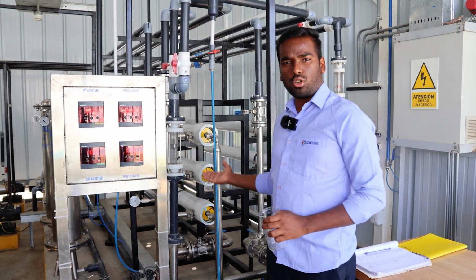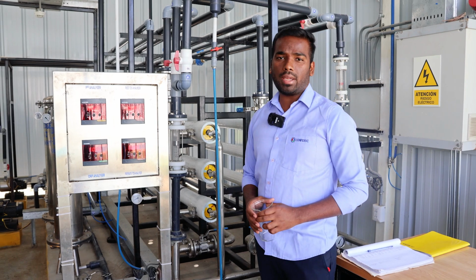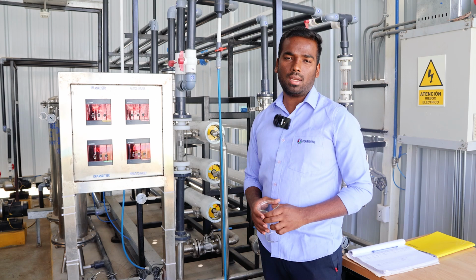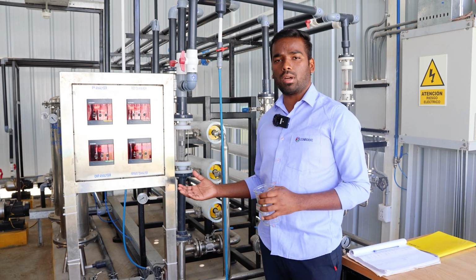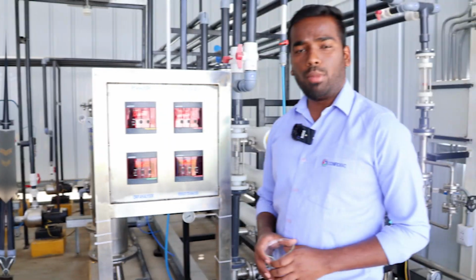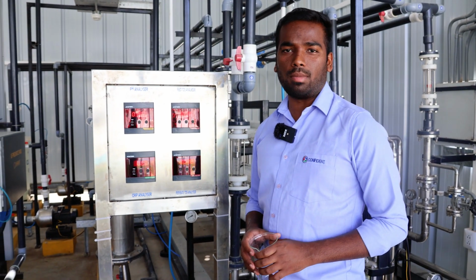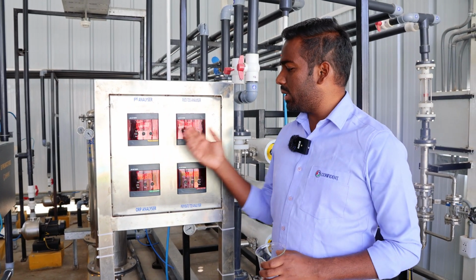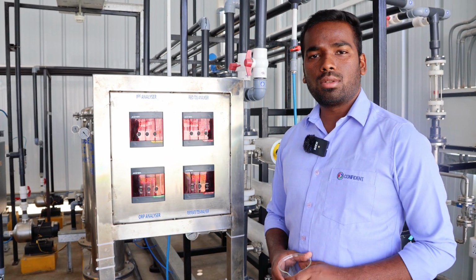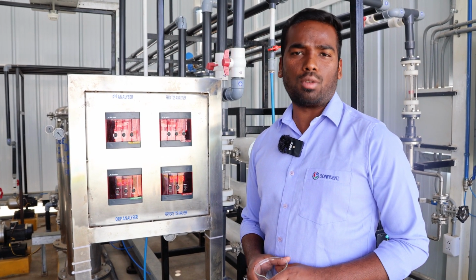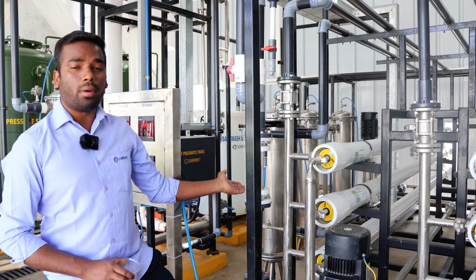It's called reverse osmosis. Here we are taking 70% permeate water and 30% reject. That 70% permeate water will go to the process of the lavanderia. Before entering the reverse osmosis membrane, we are controlling parameters like pH, TDS and ORP. Here we are maintaining a pH of 7.3. This pH is good for the process. This is a permeate pipeline.